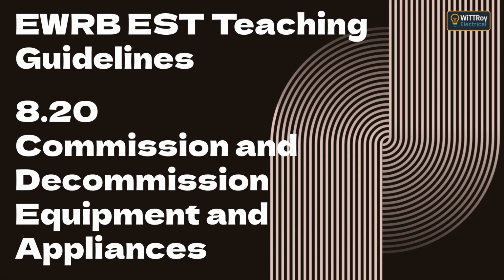Topic A, Procedures for Disconnecting and Reconnecting Conductors. Whenever we work on any fixed appliance or circuit, we must disconnect and reconnect conductors safely. This process follows the same logic as the lockout-tagout procedure from earlier topics, but now applied specifically to appliances and motors. Let's go step by step. Step 1. Isolation and tagging. Before disconnecting, always isolate the supply at the correct switchboard. Turn off the isolator or circuit breaker, lock it off with your personal padlock, and attach a danger tag showing your name, date, and contact.